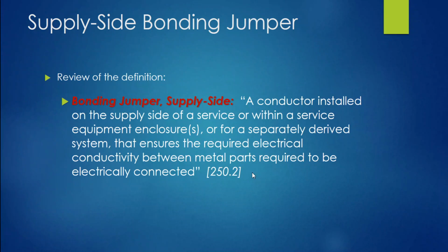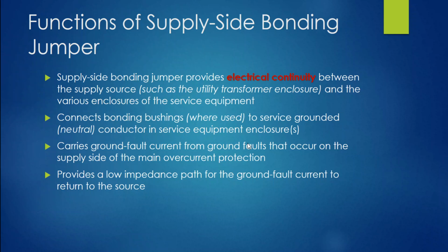Again, for the 2020 NEC, it's going to be moved over, I would assume. I can't see why not, and I sit on that code panel. And actually, we've had a meeting about this, and we've given our opinion on it. It belongs over in Article 100 because it is used in more locations within the National Electrical Code. And if you want to find that, get your PDF version and type in supply side bonding jumper and do a search, and you'll see that it comes up in a lot of different articles within the NEC. And that, of course, will be our substantiation for that within the first revision of the 2020 NEC.